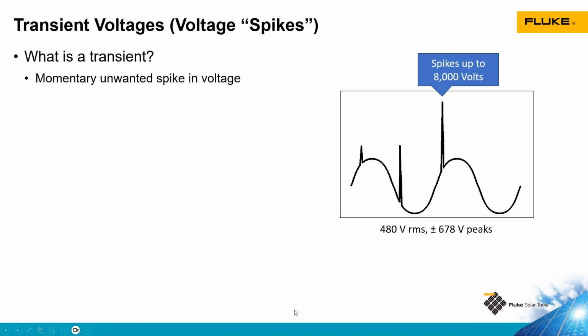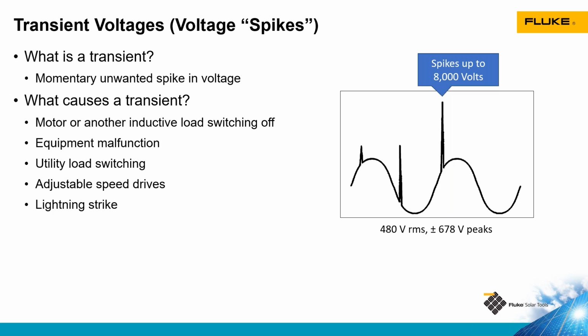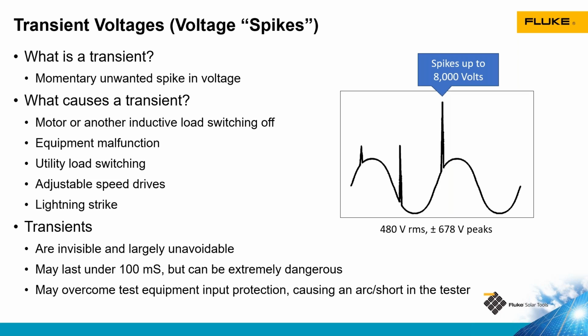The first thing we need to think about is transient voltage spikes. These are a large spike in voltage. They're very short duration, typically coming from the utility when we're thinking about solar installations. If you are working on a commercial system where you're in a commercial building like a manufacturer, you might get a voltage spike from something like a motor turning on and off. We can also get transient voltage spikes on the DC side from things like lightning strikes. They're unavoidable. They're invisible to regular test equipment. We can see transient voltage spikes with our higher end power quality analyzers, very short duration.